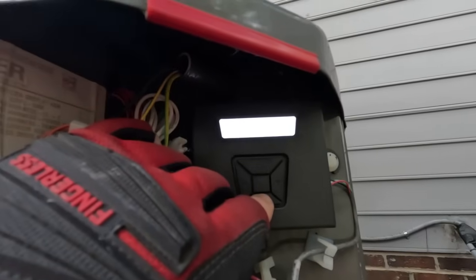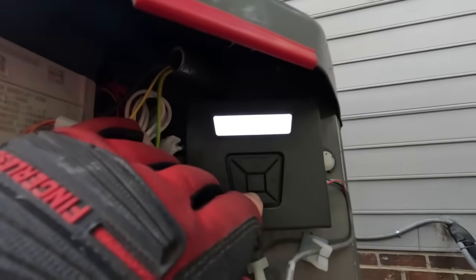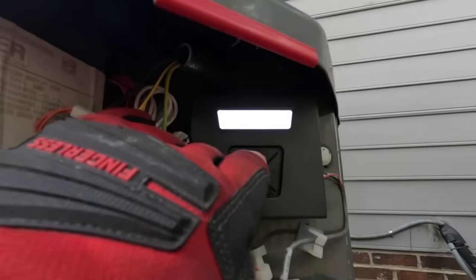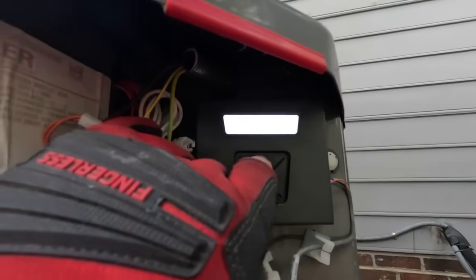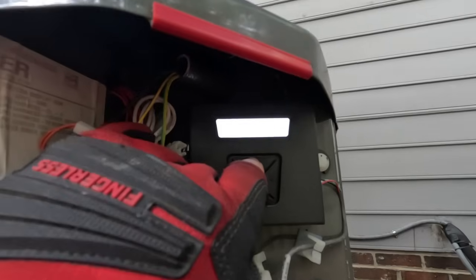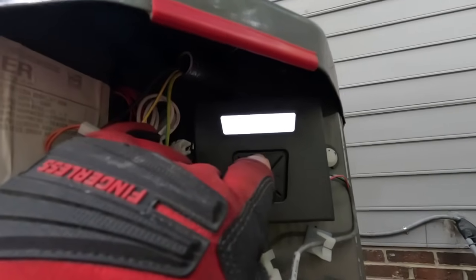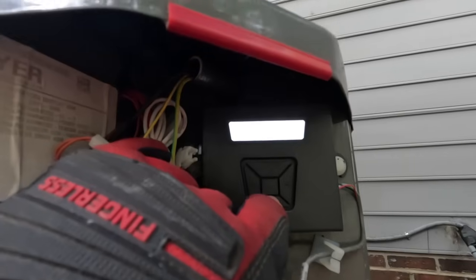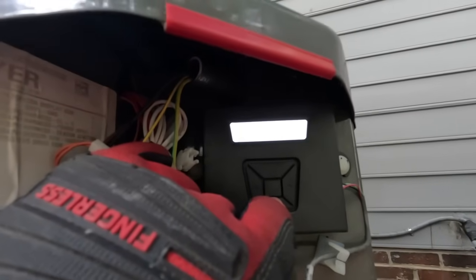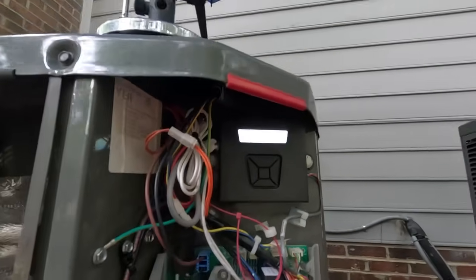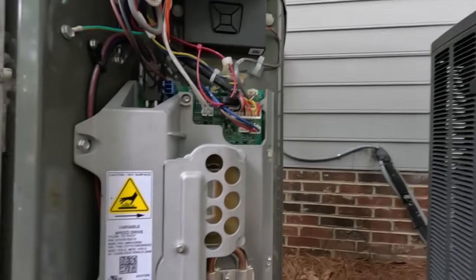But anyway, that's kind of how you go through that and look at all that, and you can go in here and find out the fault history on it, current alerts, things like that. Compressor state, yeah, see now we're all the way down to 900 RPMs. So that thing's getting ready to shut off here in a minute. Anyway, guys, another bad sensor on an XV system.